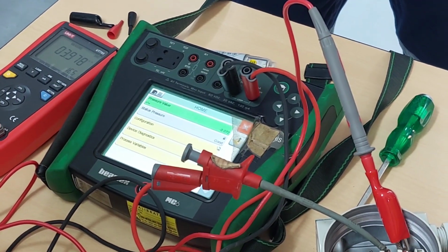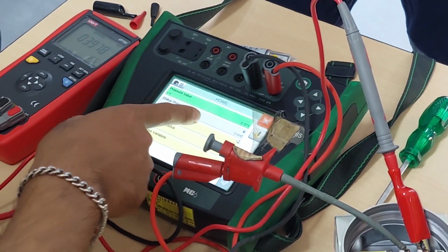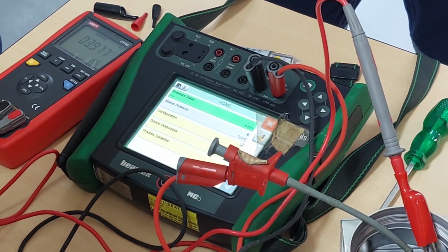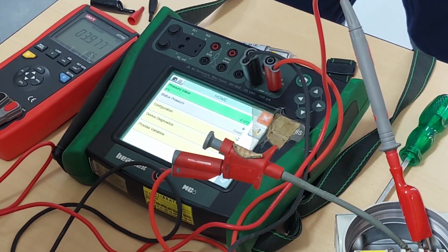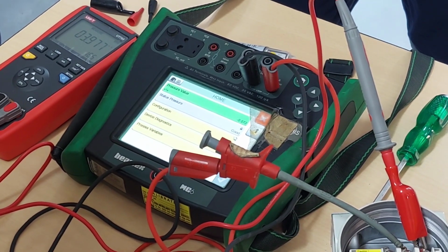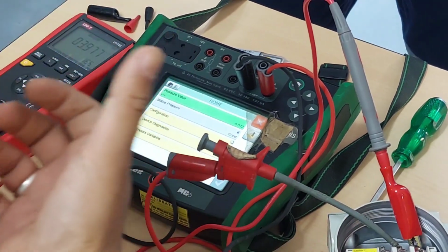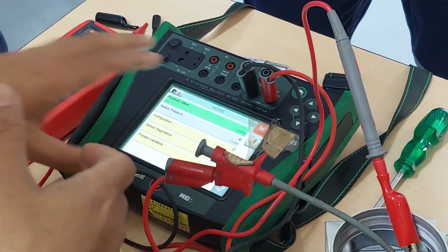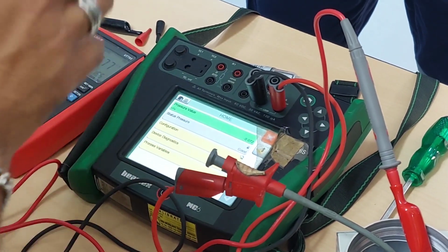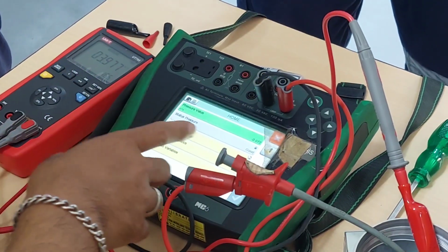Okay, so first, if it's pressure, we always zero it first. Kailangan natin i-zero. Let me just find where it is. Now, why? Because Siemens is not the same as Rosemount. Rosemount is what I am used to. And every transmitter, every model has different screens. So we'll be looking for zero.